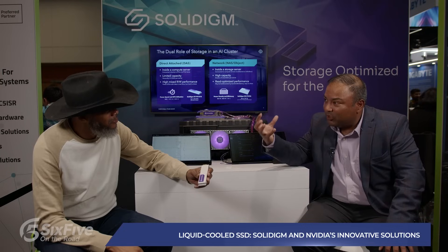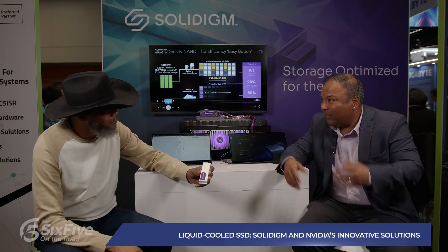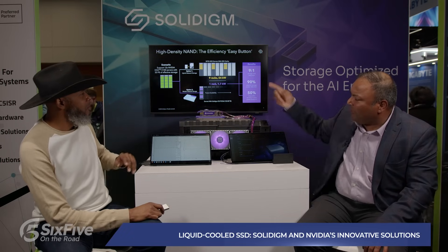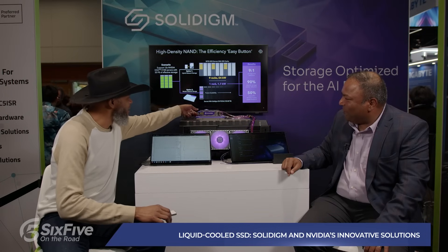Before the demo, I don't see where you put the tubes. There are no tubes! You connect it to the lid cold plate, and the cold plate touches the front and back side of the SSD. We have an internal mechanism and thermal management designed as part of our solution so both sides get cooled, giving you active cooling support across the full SSD. Pull one out, Keith — go ahead! Last time I pulled a drive out of production the whole system went down... We're fine, go ahead.